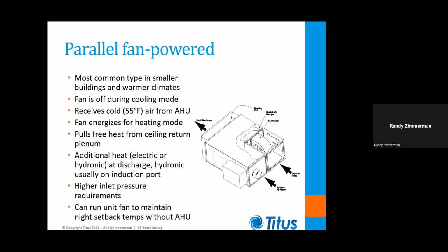And of course, this is a parallel fan box because the primary airflow is moving in parallel to the fan airflow. The primary airflow goes around the blower and out to the room. The return air goes through the blower, mixes with the primary air, and goes out to the room. Now you'll notice there's a backdraft damper on that fan. And that's critical because when the fan's not running during the cooling mode, you don't want your primary air to dump out that induction port. So you've got usually a gravity operated backdraft damper that flops down and closes off the discharge to the fan to block that primary airflow.